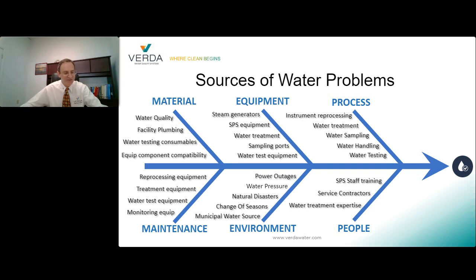A comprehensive water analysis told me in one week something they hadn't been able to determine over months - that after all the other factors that may contribute to the issue, it was poor quality steam feed water and an undersized SPS-dedicated boiler that were the main culprits.